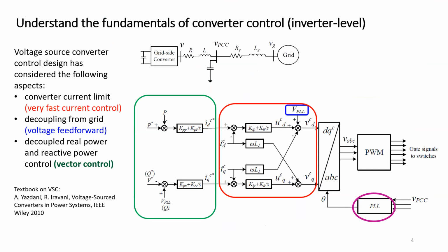Here I'll talk a little bit about the fundamentals of converter control. Everybody is pretty familiar with grid-following control, which has 3 components: a very fast current control, an outer loop with vector control for decoupled real power and reactive power following, running slightly slower, and then a phase-locked loop conducting synchronization. This material has already been published in a 2010 textbook.